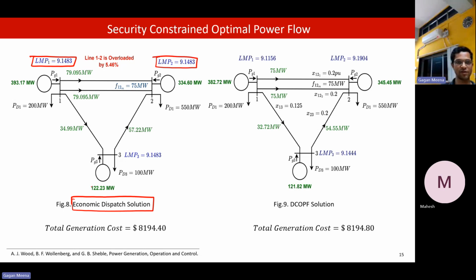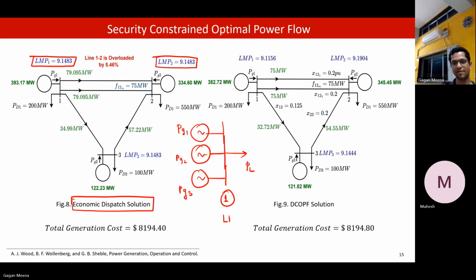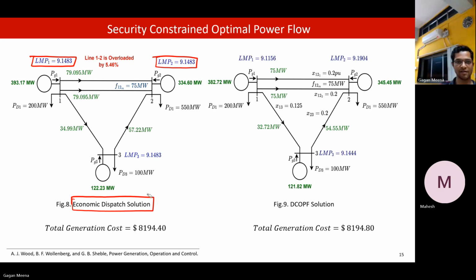In this case, we saw that one of the applications of OPF is to do economic analysis, and we can find out the LMP, locational marginal pricing. Here you can see the output of this problem is also LMP. Because this is simple economic dispatch, the network is not considered here. That is why the LMP will come out to be the same for each bus. It is as if all three generators are supplying the load on bus 1, let's say. All the generators are connected directly to the load. There is no network. In that case, there will be only one incremental cost. So that's why you see LMP here is 9.1483 for all the buses.